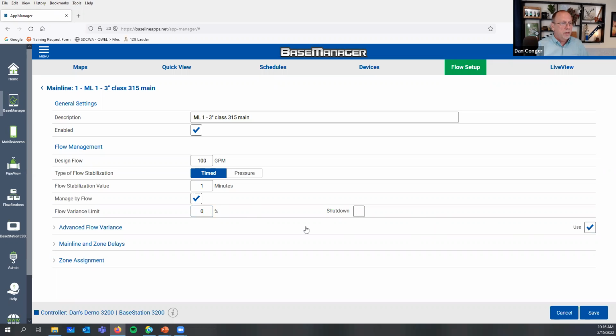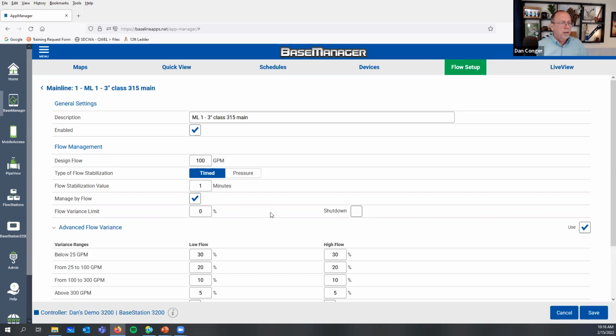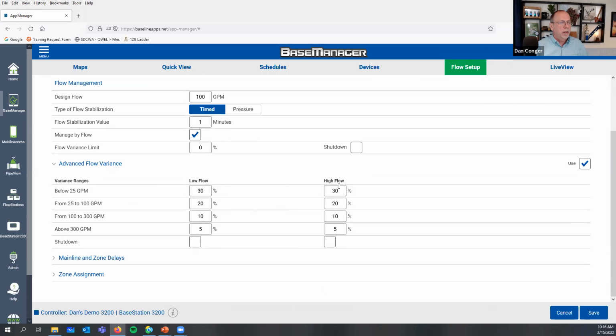what I really like is this advanced flow variance here. And I've already set up some limits on here, and this has different percentages, which is really nice to have a very high flow percentage range on low flows, and then a lesser tolerance on highs. But right here, I can shut down for high flows, shut down and alert for high flows, but not shut down for low flows, but just get an alert. So I think you get the best of both worlds with this.